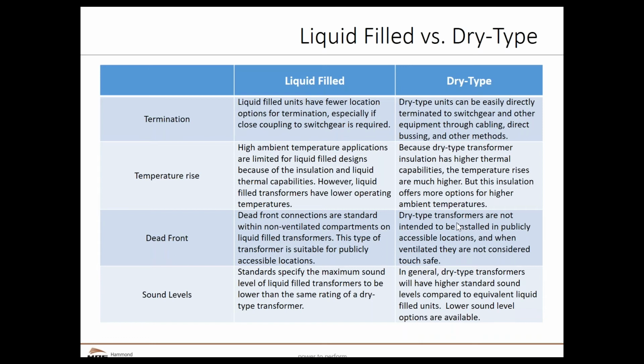Dead front construction is very typical with liquid filled. Oftentimes it might be part of a larger utility requirement, which could be very important within the installation of that transformer. Dry type transformers can be built with a dead front construction. It's not as typical as it is with liquid filled. We have done it, we do it all the time. But again, it's something that is a little bit different.